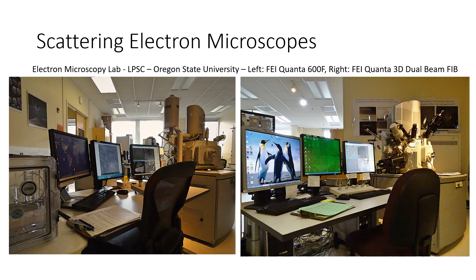Let's discuss electron microscopes. As you can see, at the top of a particle accelerator, there is a tungsten filament that produces plenty of electrons and then accelerates them across the voltage, generally 2000 to 30,000 volts. Because they are charged particles, we can use magnetic fields to focus the electrons to a very fine area. Electrons have a much higher resolution due to the shorter wavelength than light. So when you're looking at an electron micrograph, electrons are smashing into the sample, exciting secondary electrons that are collected and used to produce an image.